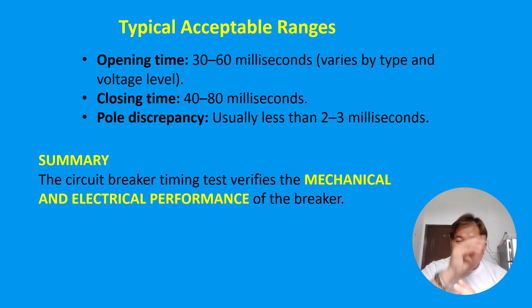In summary, the circuit breaker timing test verifies the mechanical and electrical performance of the breaker. Why are we talking about mechanical? Because you operate it manually, right? And then we have the electrical connections to our system. Regular testing helps ensure the breaker will operate quickly and correctly during faults, preventing equipment damage and maintaining system reliability. That's why it's required, and everyone knows the circuit breaker, right? So what is a circuit breaker? It's very simple: on and off. But there are important things that we need to do for our breaker, especially in the oil and gas industry and refineries. We have to test the timing, closing, and opening. All of the parameters are important.